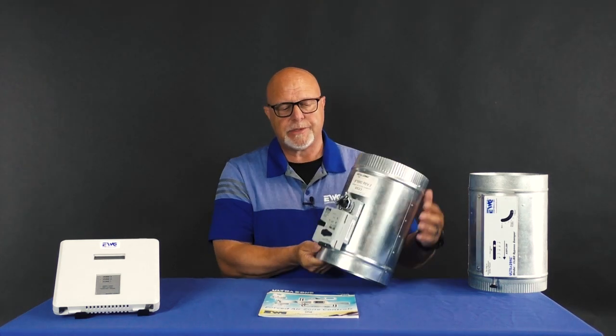Once you have your system operating in your most critical situation, you want the highest output in fan, you want the highest output in system output. You want all the zone dampers that I have gone over previously in this series. You want all of those in the open position.